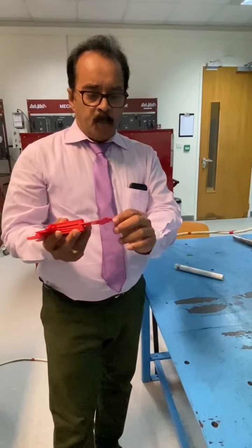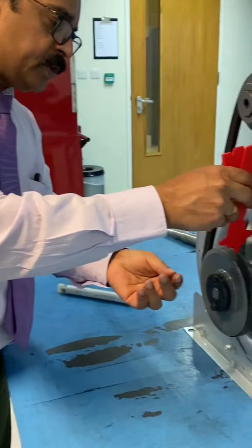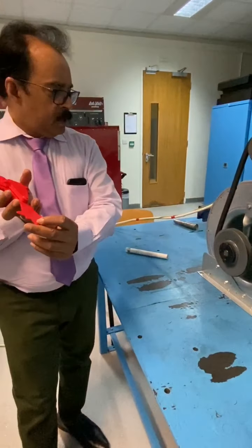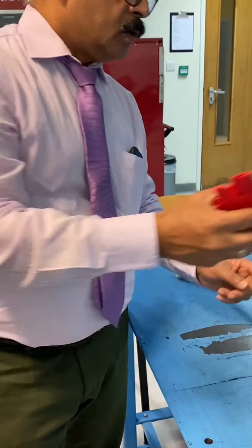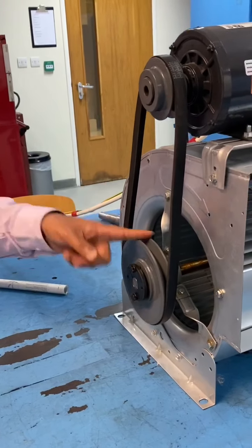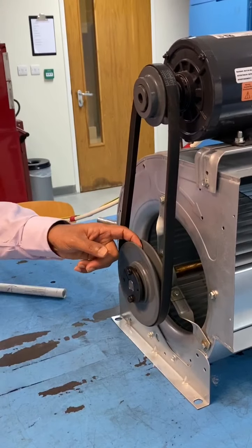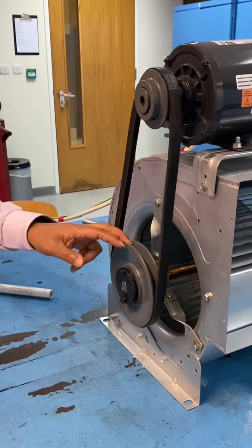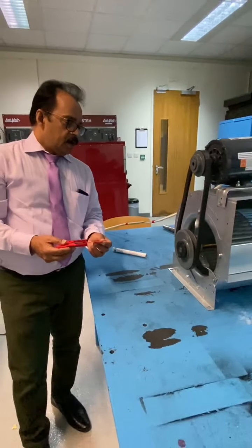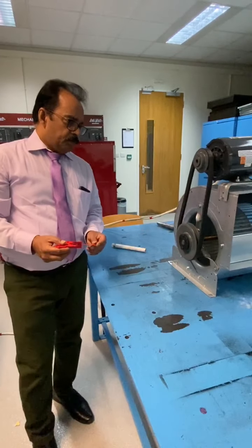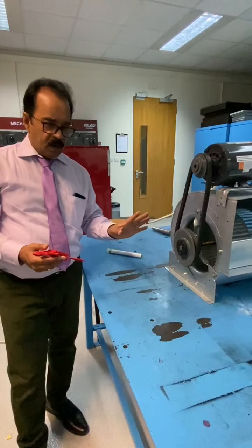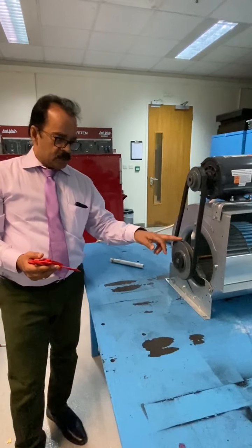This is the groove pulley gauge. By checking here, the angle is around 40 degrees. If there is a gap between the groove, it means you need to replace the pulley. Here, for this pulley and that pulley, this angle is different, this angle is different. So you must check the groove pulley angle, and once it meets the specification mentioned in the catalog, it means it is okay. Otherwise, you need to replace the pulley.